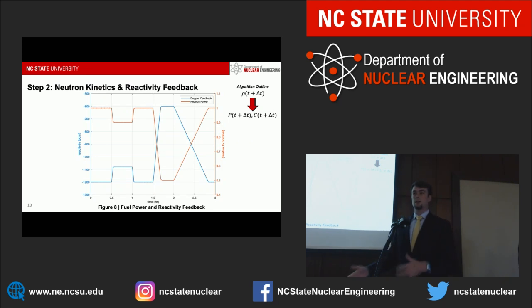So the control rods move, but there are also more reactivity feedbacks included in the calculation. So we solved the one group point kinetics equations to include the reactivity feedbacks from void, fuel temperature, xenon, and control rods. So as the fuel temperature goes up, the negative reactivity from fuel also increases, and the other reactivity coefficients also provide their feedback. And those are calculated every loop to manage the reactivity balance and therefore change power level.